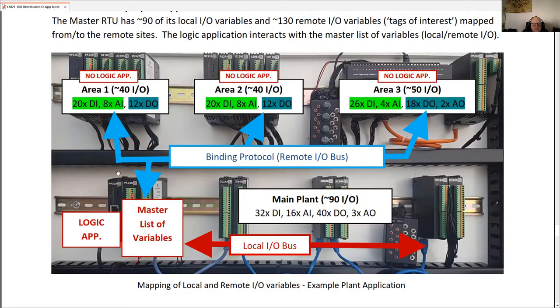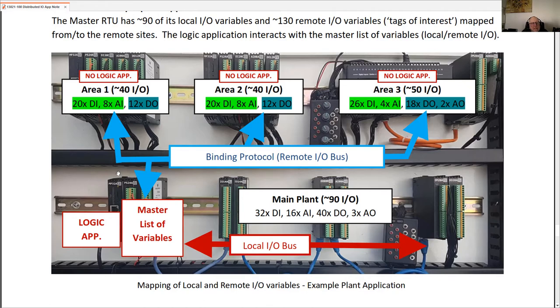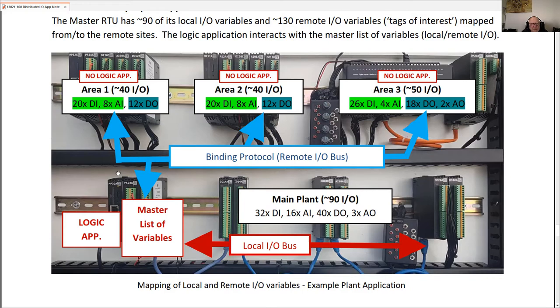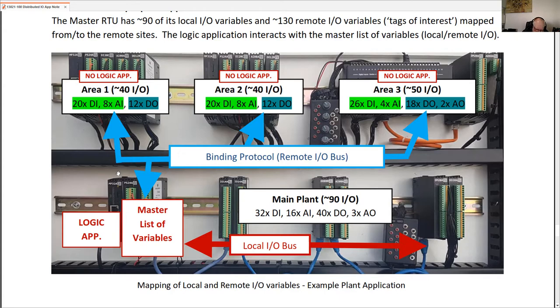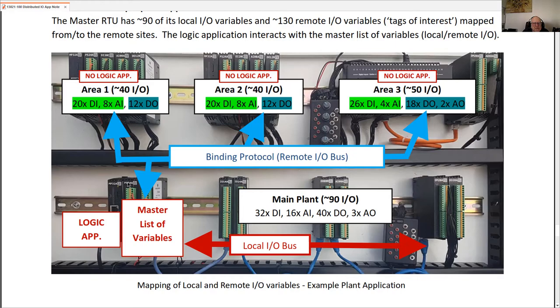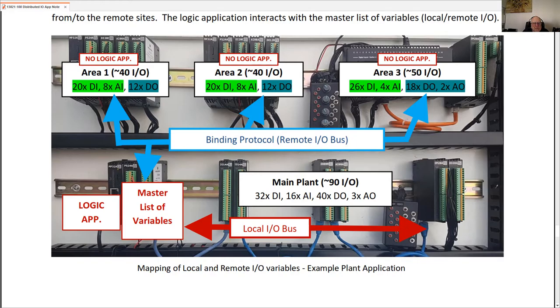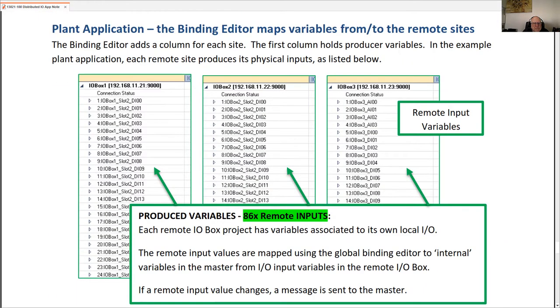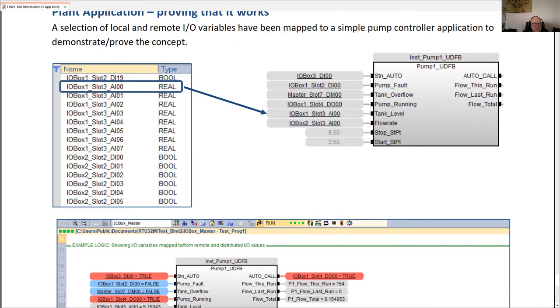This is my sort of primary demo. The idea being you have some segmented I/O at the bottom there, that main plant. I've got a 35 meter bus stretched out all those modules. Then across the top I've got three different RTUs. They're just very simple CPU setups, no license options, they're just behaving like remote I/O. And if you needed to change your mind later and put some logic, you can just make them able to stand alone or do some local plant control as well. Future proof.